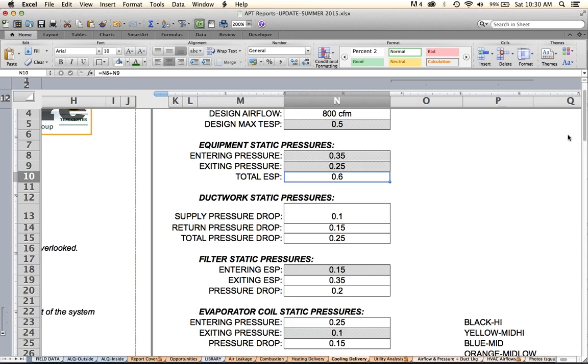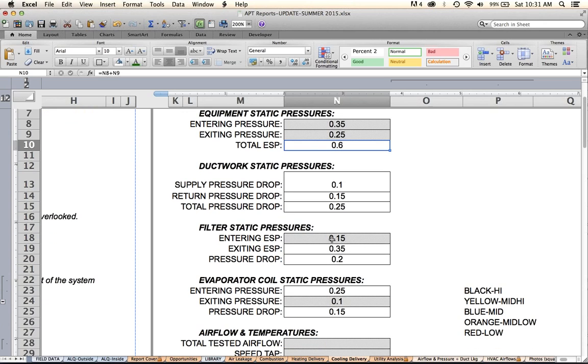So what we want to do is figure out where it's coming from. So the supply pressure drop is 0.1, and that's actually what you're aiming for. That's always good. 0.15 for the return means that the return might be a little bit undersized or taking too many turns, things like that. So we want both of these to be about 0.1, the way that I understand it. And again, not an HVAC expert. In fact, I get corrected all the time. And so I say things and people correct me. So feel free to correct me if you do know better.